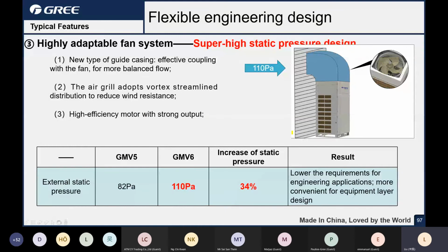A lot of improvements are about the air duct, the outdoor units' air duct. For the GMV5, it's just 82 Pascal. For GMV6, it's 110 Pascal. That means you can install a longer discharge duct when you install the outdoor units in the basement or some closed area. That's good for your construction.